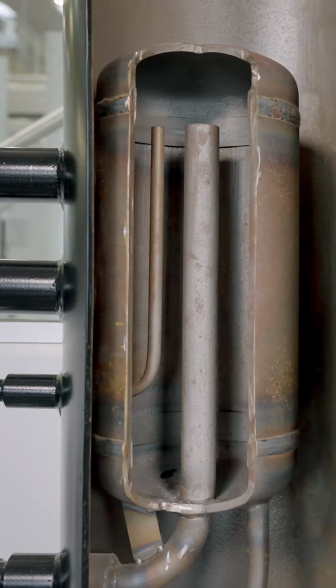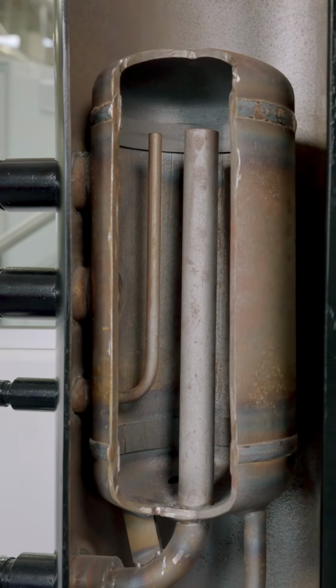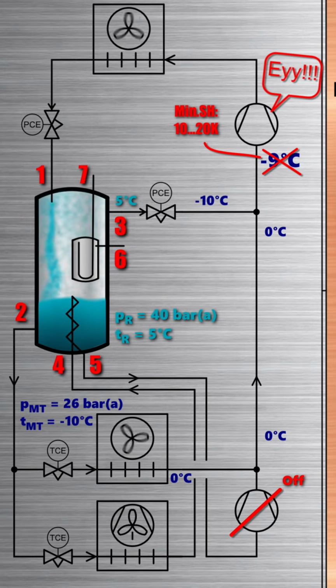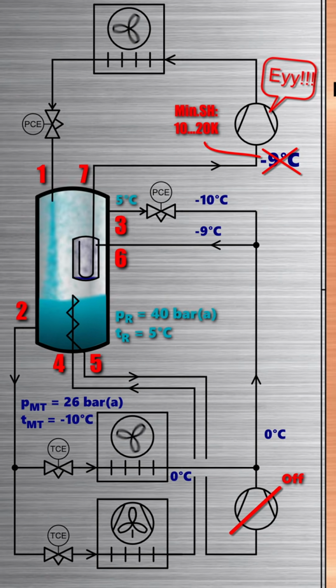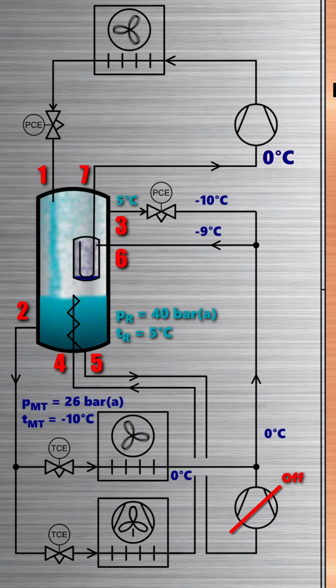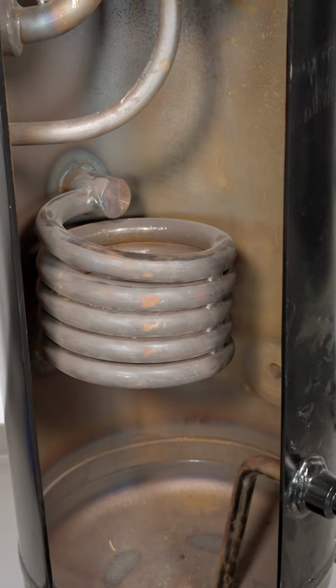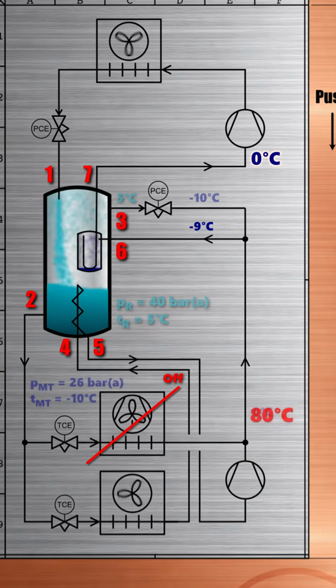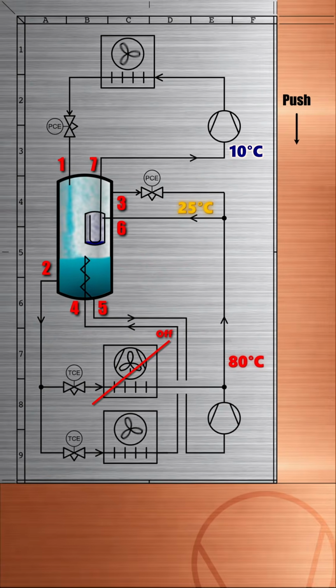The vessel inside the receiver solves that problem. It's essentially an external heated liquid separator. It keeps the liquid out and improves the suction gas superheat, just like the heat exchanger. It also adds cooling when only the low temp stage is running. These are three more ports on the receiver.